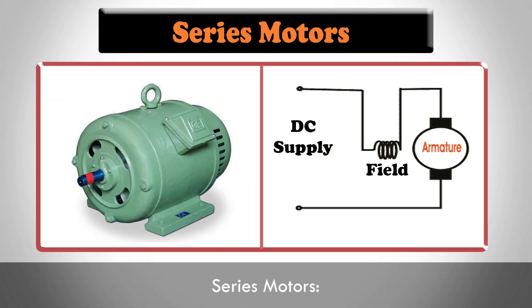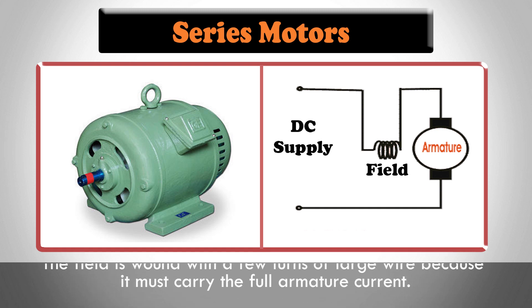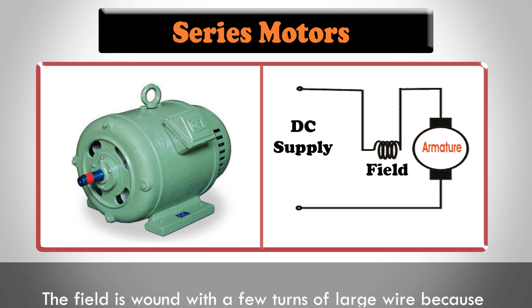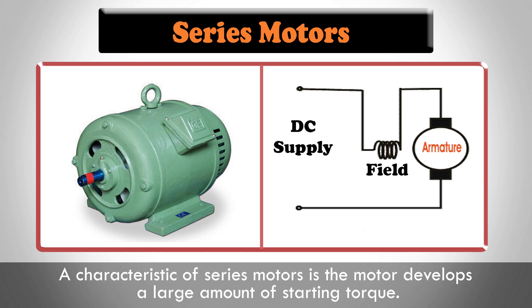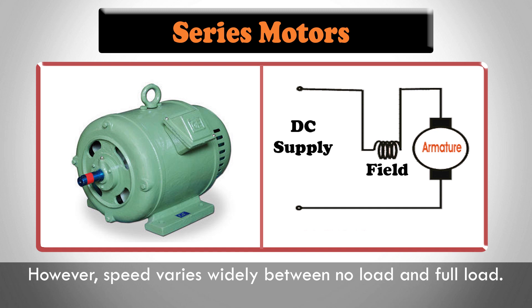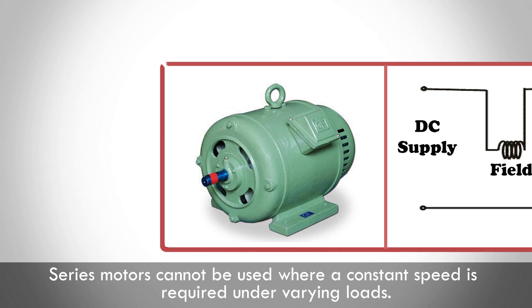Series motors. In a series DC motor, the field is connected in series with the armature. The field is wound with a few turns of large wire because it must carry the full armature current. A characteristic of series motors is that the motor develops a large amount of starting torque. However, speed varies widely between no load and full load. Series motors cannot be used where a constant speed is required under varying loads.